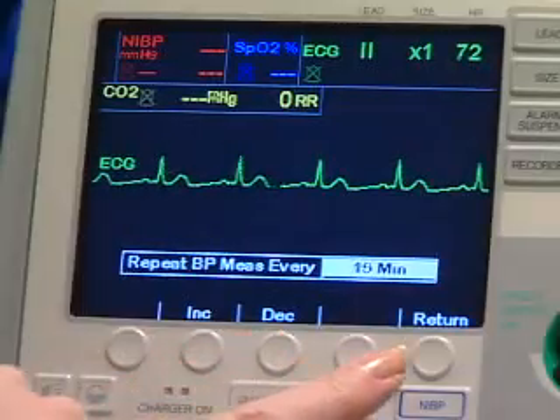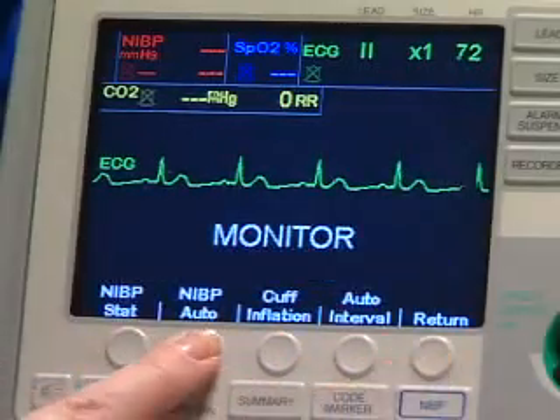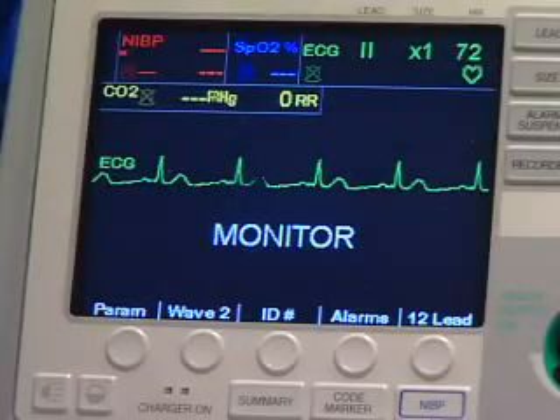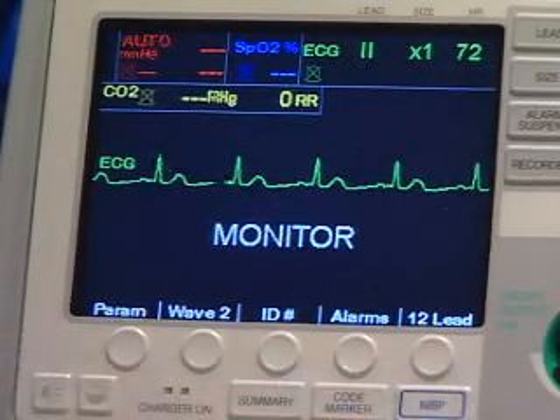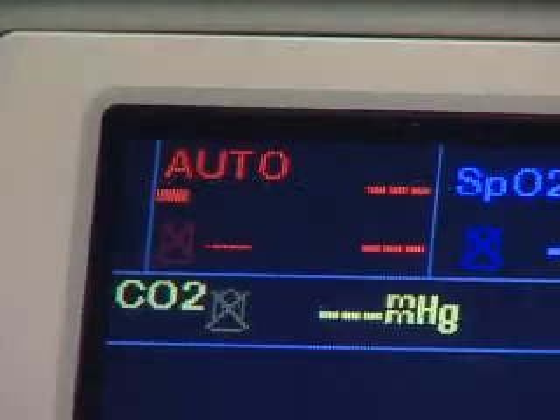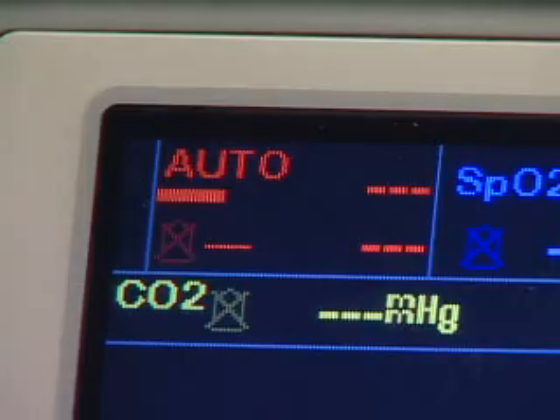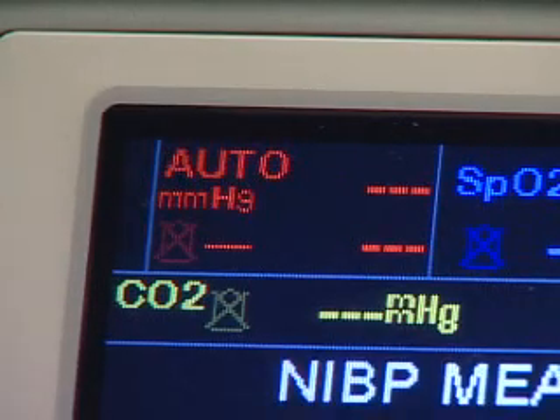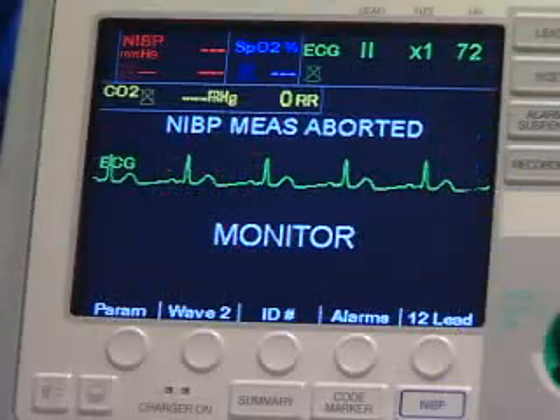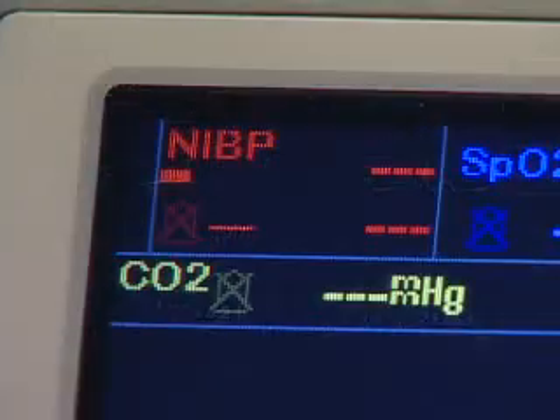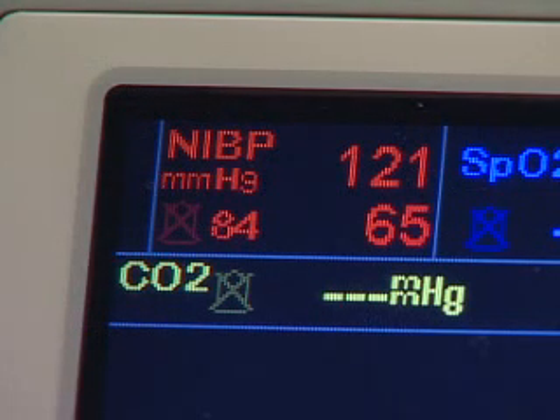Then press the NIBP Auto soft key or press and hold the button on the front panel. To stop the process, press the NIBP button. If after 180 seconds the unit has not been able to determine systolic, diastolic, or mean pressure, it aborts the measurement and deflates the cuff. After each measurement, the NIBP display area displays systolic, diastolic, and mean blood pressure values.